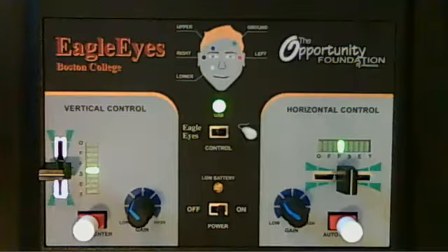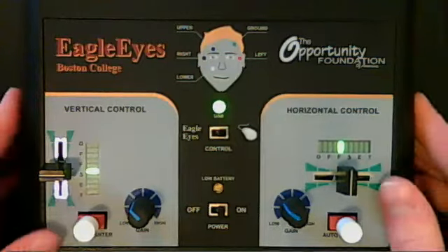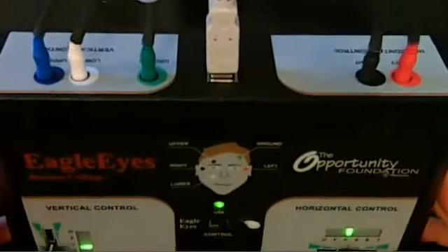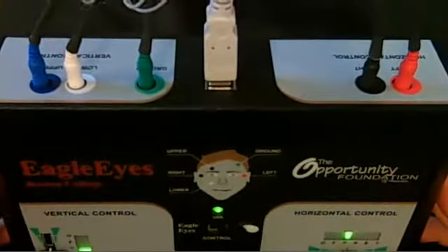So the electrode cables are a specially designed cable assembly. The cable assembly is shielded to prevent interference with small electrical signals, but we still recommend that you keep it away from any small electrical devices such as motors, fans, computers, especially cell phones, feeding pumps, or other electrical accessories. And when connecting the cable assembly, simply connect the colors as indicated, red on red, black on black, etc.